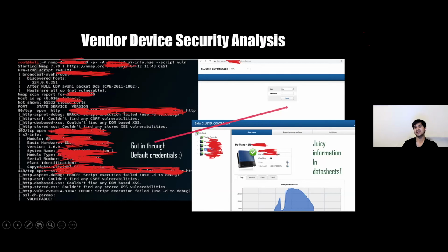So I got excited. I had default users. Immediately I looked up the datasheet for this model, and it had default credentials: user 0000, installer 11111. I immediately entered one of these credentials, and with fingers crossed, it fortunately got me in. Once again, I had complete control over the HMI, which not only allowed me to view the power plant information, but also let me edit instantaneous values and change some of the privilege settings within this panel. So yeah, there's some fun stuff that can be done with this panel.